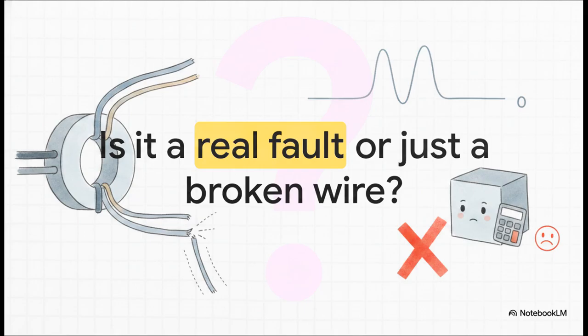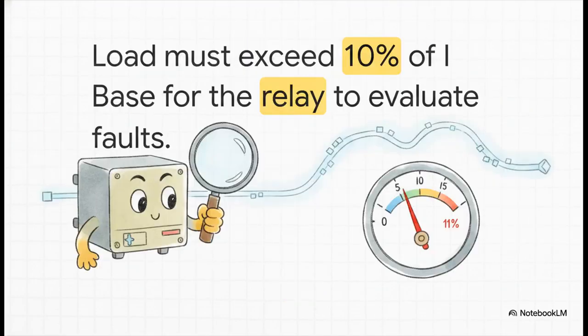And remember our strict accountant? The differential relay will see that massive mismatch and could very easily misinterpret a broken wire as a catastrophic electrical fault. It would literally shut down a perfectly healthy power line. But thankfully, specific smart relays, like the RED 670 for instance, act as digital detectives to solve this exact issue.